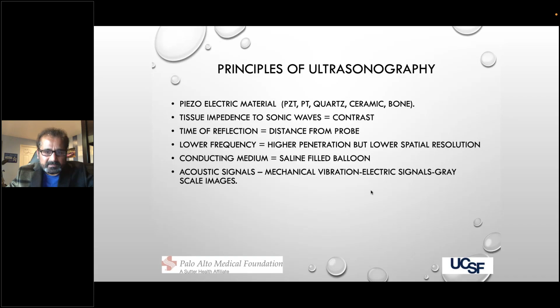The lower the frequency, the higher the penetration, but lower spatial resolution. For example, the cardiac echo is about 5 megahertz. Standard endobronchial linear ultrasound is about 7.5 to 10 megahertz is what we generally use, although there is a wider range that the system allows you to do. And radial probe ultrasound is about 20 megahertz. So the acoustic signals based on tissue impedance is converted into grayscale imaging, which is what we basically look at.